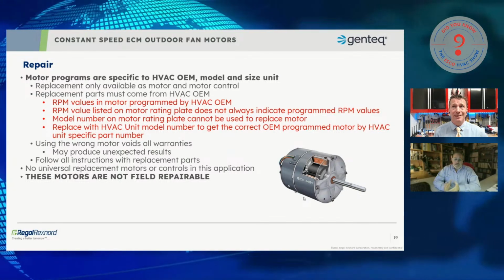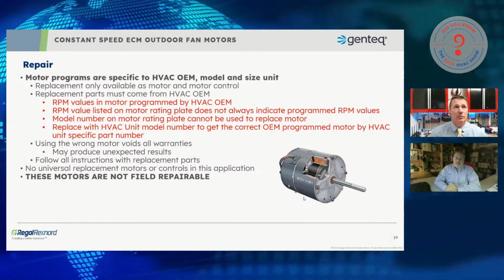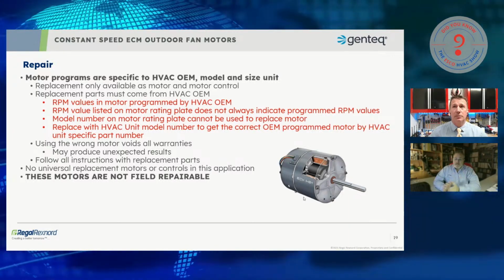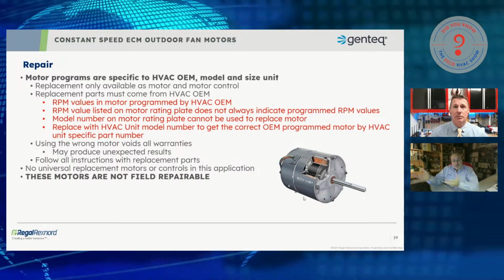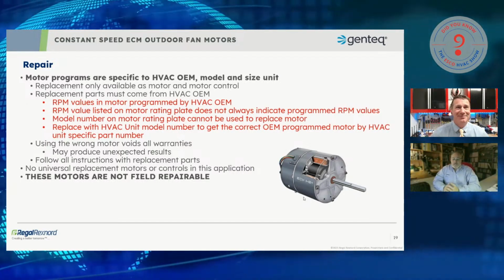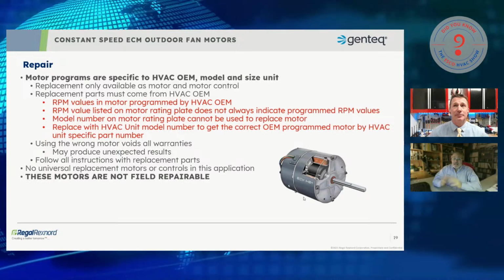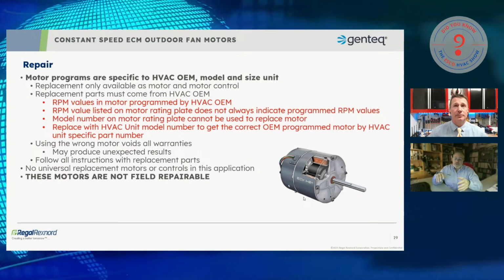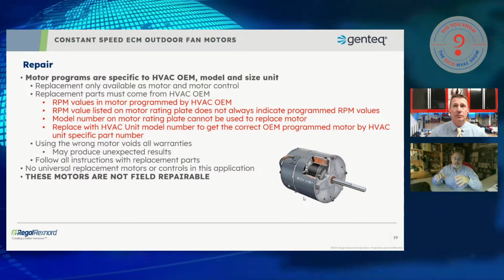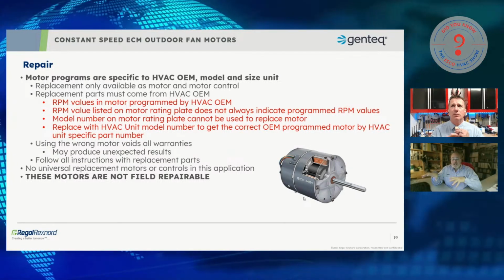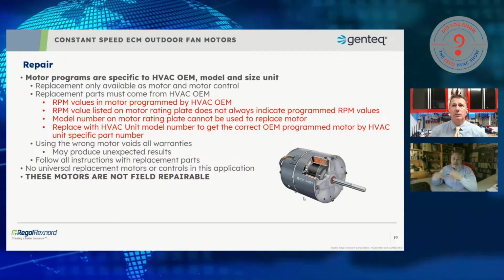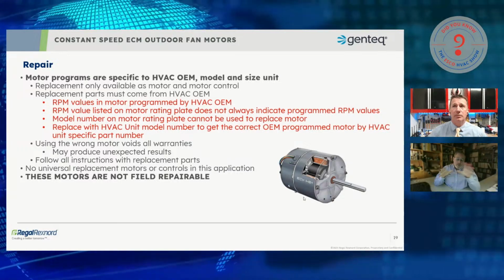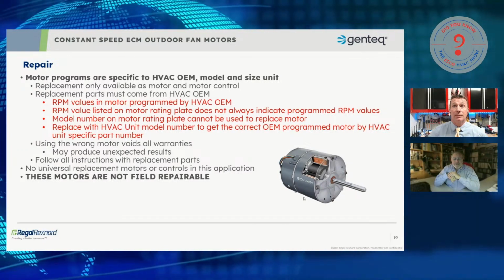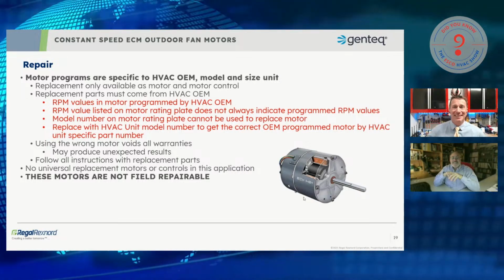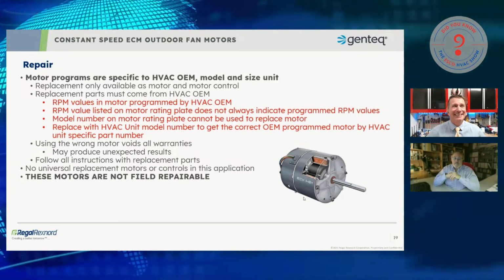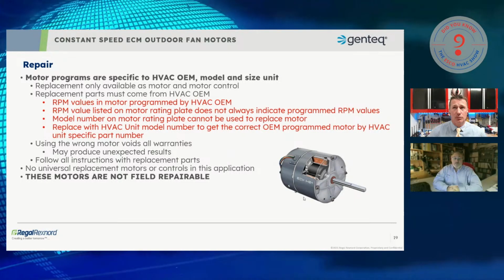Well, yeah. And I believe, if I'm not mistaken, many of them are making their own blades now because since ECM, and I say since ECM, which is 22 years ago, they can now develop the blade any way they want to, right? The blade manufacturer has more flexibility in the design of the blade than they did before, because before ECM, it was, you got to make it work at 825 or 1075. That's it. Right. I mean, you could run it at 1625 if you want to, but that's going to be really noisy sitting next to the bedroom window. Exactly. So, they were stuck with those two operating points. Now they've got 600 to 1200 RPM to play with.